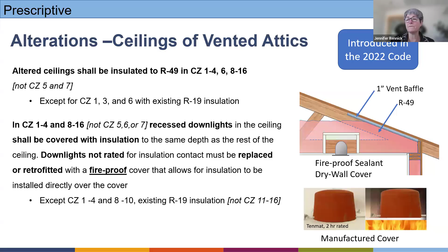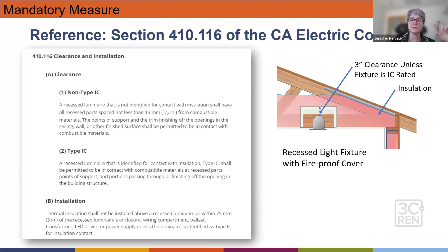And also for existing recessed lighting, they do need to have a fireproof cover put on them unless you're replacing those light fixtures. And at that point, you can have insulation-covered, rated recessed light fixtures. So that's going to remain the same. And just as a reminder, that part of the code really references back to the electric code and spells out a little more clearly what the clearance is needed. And if you don't purchase an already made recessed light cover, you could create one out of drywall. Just need to make sure that the joints are sealed, and that you have a 3-inch clearance above that fixture to the bottom of your drywall cap.